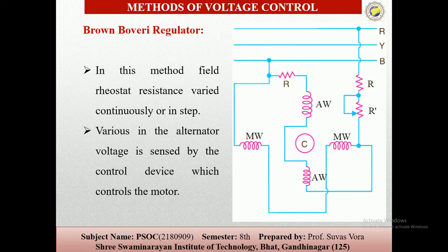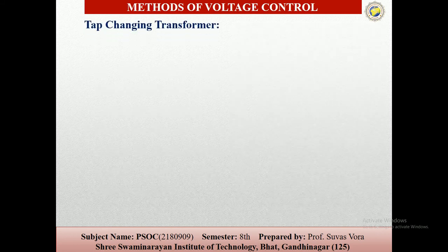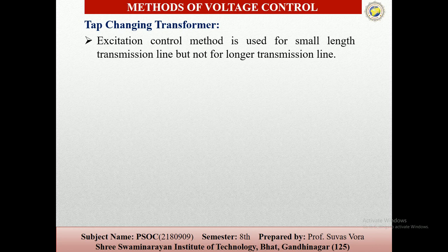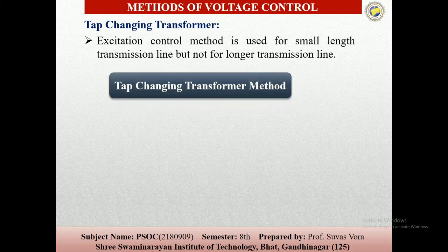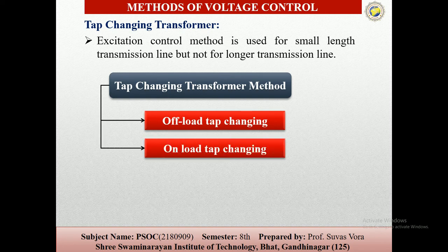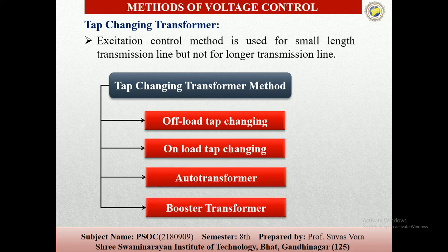So in the last lectures we saw this. Then we look at the tap changing transformer. The tap changing transformer is again nothing but a regulator. The excitation control method is used for short transmission lines but not for long transmission lines. The tap changing transformer method has off-load tap changing and on-load tap changing systems, an auto transformer system and booster transformers. Off-load tap changing is when the load is not connected to the supply; at that time we can change the tap of the transformer. On-load tap changing is when the supply system is connected; at that time we can change the tap of the transformer.